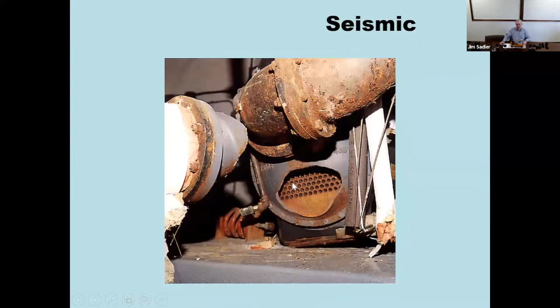So those of you in seismic zones, you have an additional challenge, right? You want the system isolated, but you also want to incorporate seismic snubbers that keep the equipment in place in the event of an earthquake. So there's another selection table for seismic zones. That same pump we looked at for isolation, now let's put it in a high seismic risk area.